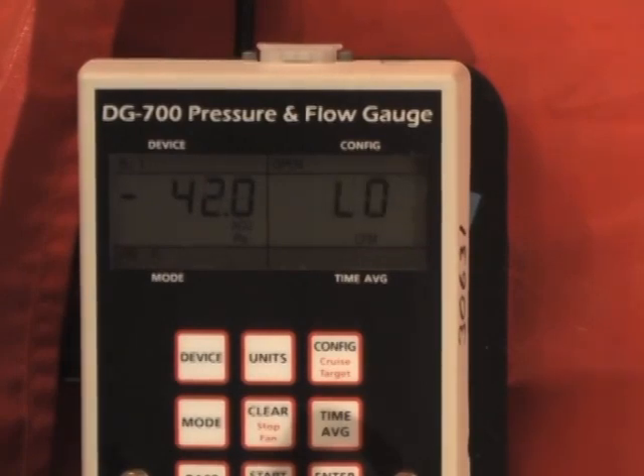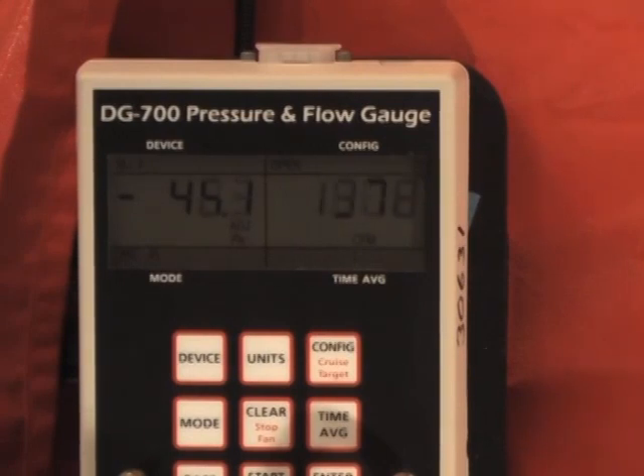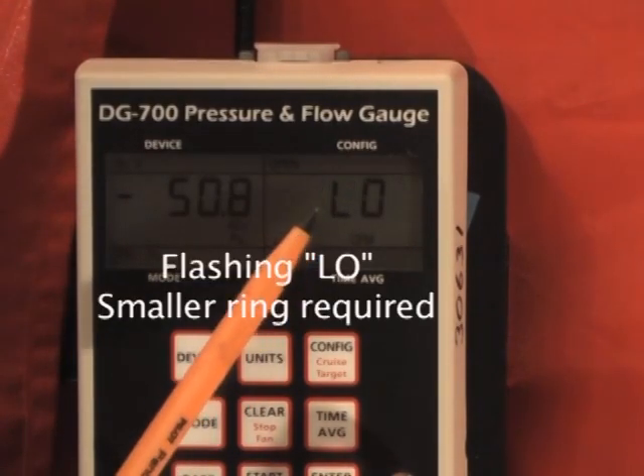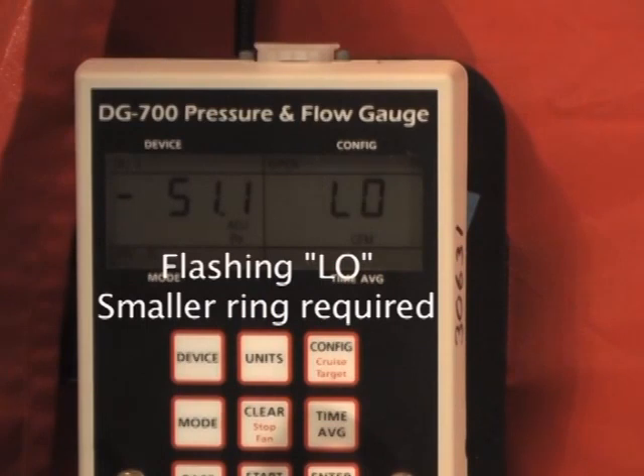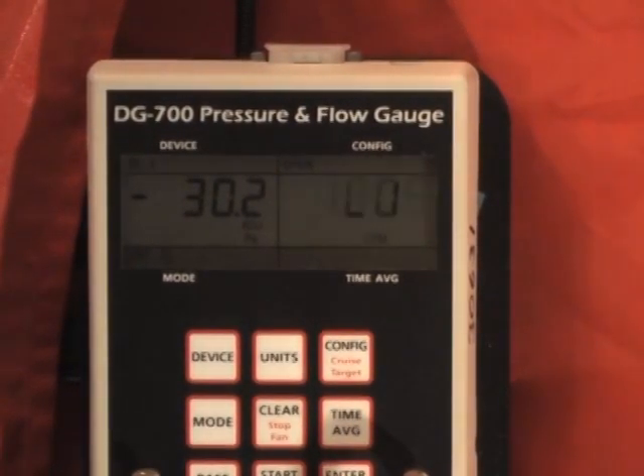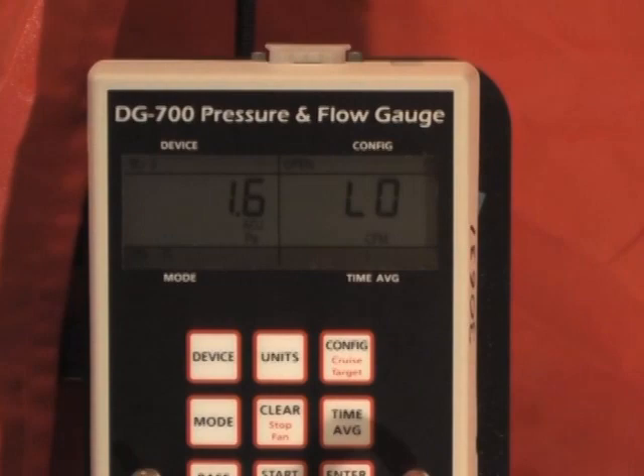We're at about 42 pascals now, and we're about at our test pressure. But you can see that this is flashing between low and 1900-something. What that tells us is that we have the fan in the wrong configuration—that the house is tighter than we can measure using the open configuration on the fan. Simple procedure to correct that: we simply turn the fan back down, and we're going to install the A-ring and reconfigure our DG700.